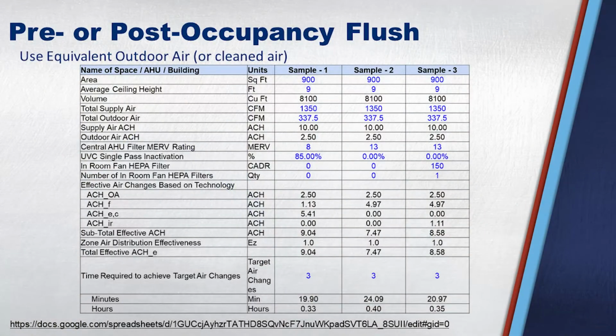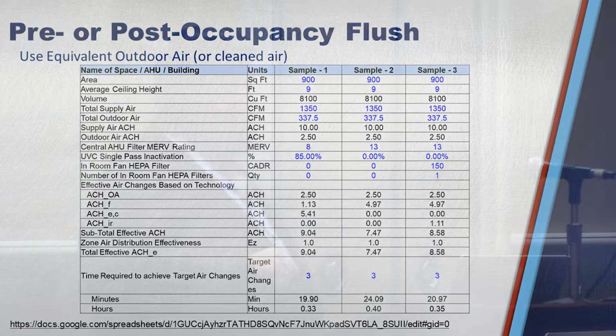So this is the data that's shown in the sheet. The calculator, you're putting in anything blue. This is a middle school classroom that we evaluated, 9-foot ceiling, supply air, outside air that is code minimum. And then you can see we changed the MERV filter, and that's pulling from that table that we showed. We have UV with a MERV 8. You can see each component, but it's saying your effective is 9 air changes of equivalent outdoor air. MERV 13 with no UV, no in-room, I'm at 7.5. MERV 13, I can add 150 CADR from an in-room, and I'm back up at 8.6.